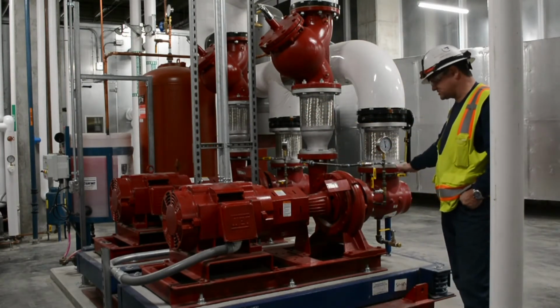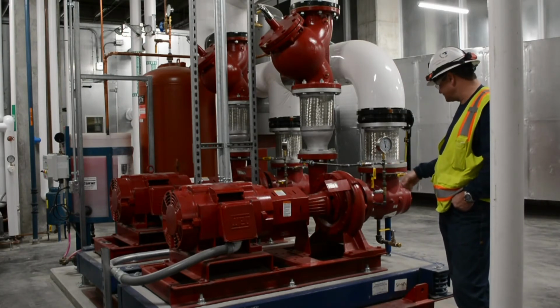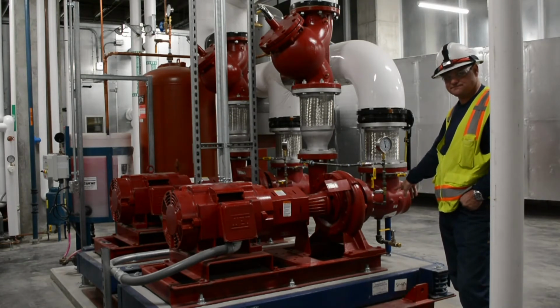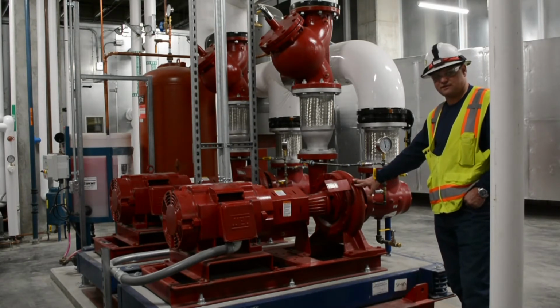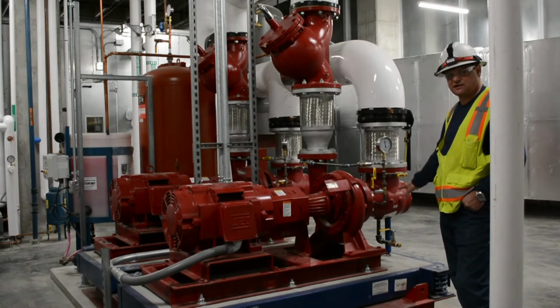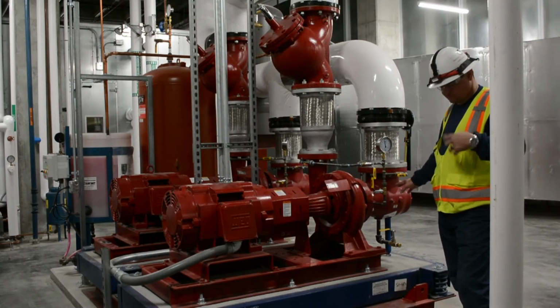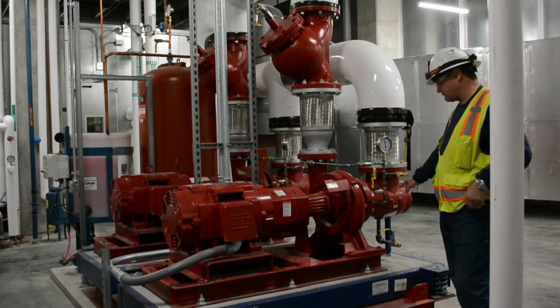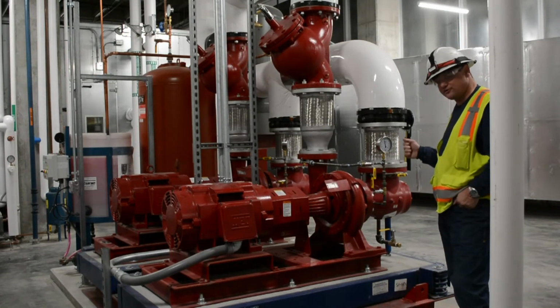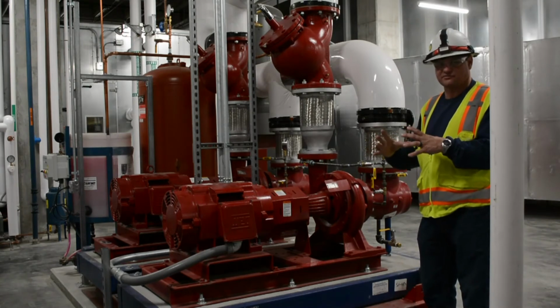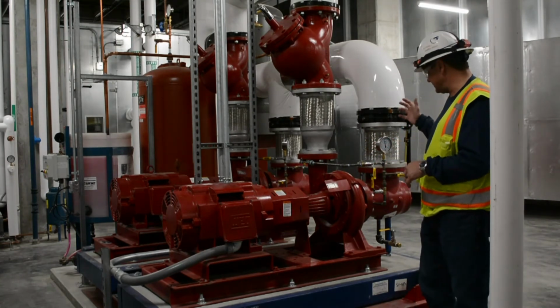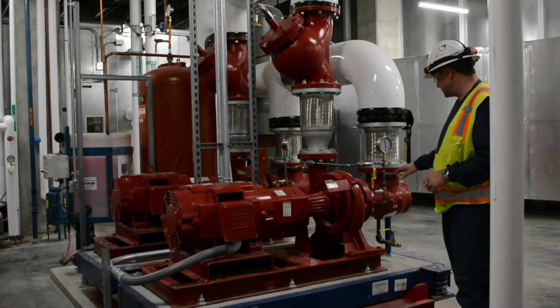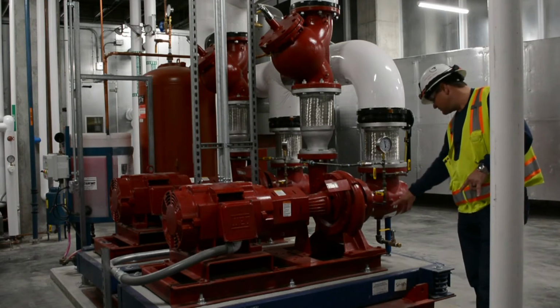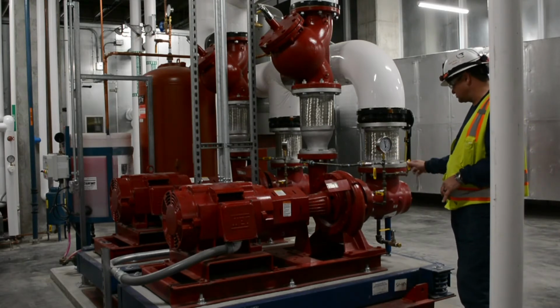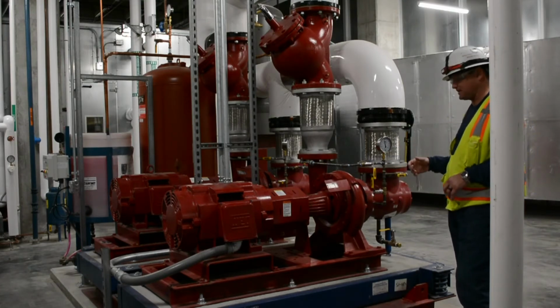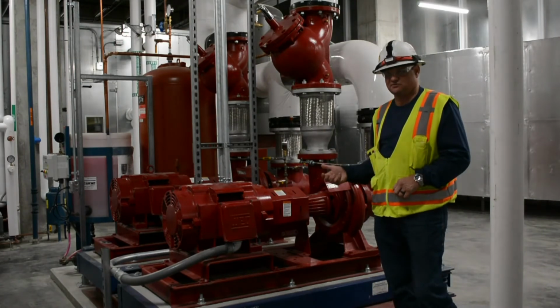At the back section here is the suction side of the pump. This is where the water enters the pump volute, and in that section there is a basket strainer to protect the mechanical workings of the impeller. That does need to be inspected occasionally. We obviously have cleaned and treated the piping system, as with all of the other systems, and have pulled the startup strainers out of there, and now it's just the simple basket strainer with the 1/8 inch relief holes, and any debris can get collected there, and you'll want to monitor your operating pressure across this strainer section with this gauge. You can valve it to see what the DP is across it. Once the DP gets above a couple of pounds differential, you'll want to inspect it.